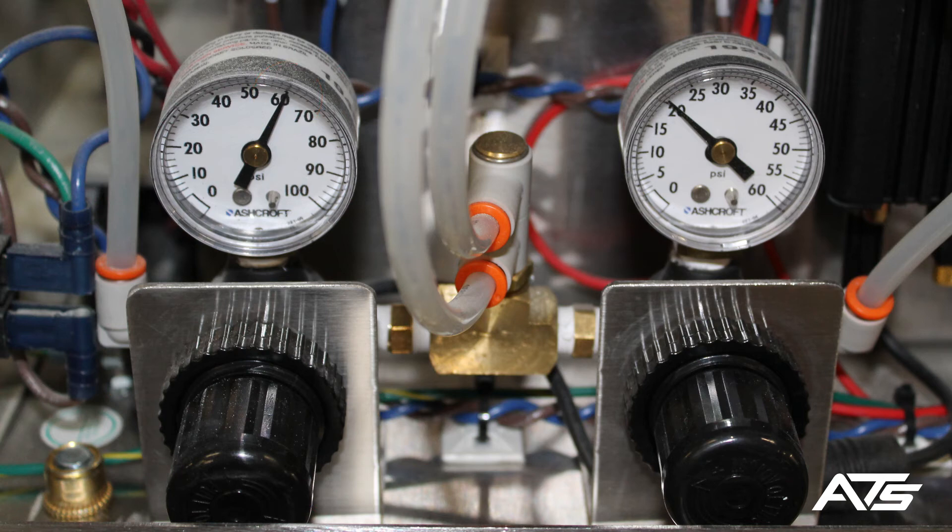The bearing pressure regulator is located to the right of the line pressure regulator and is set at 20 psi. Before using the BBR, ensure that both regulators are set to the appropriate pressure.